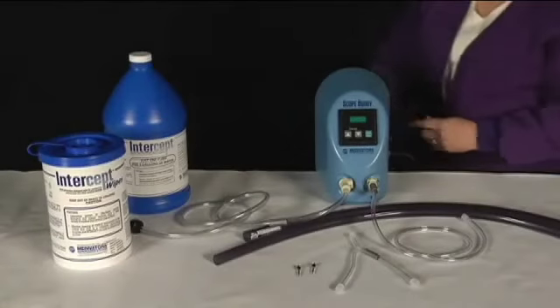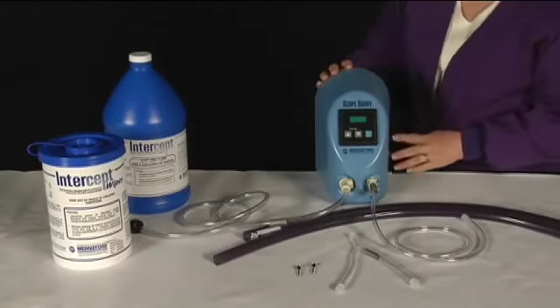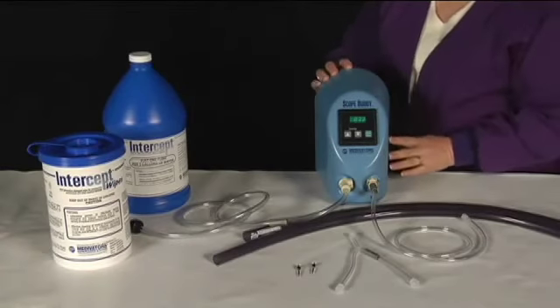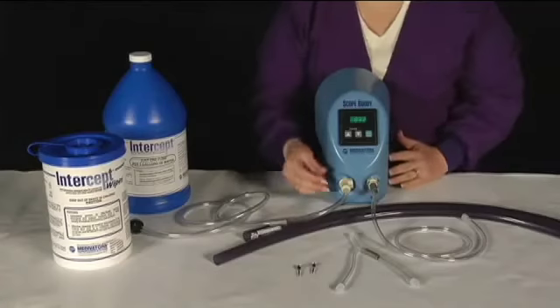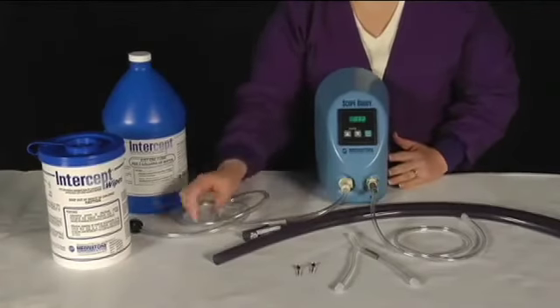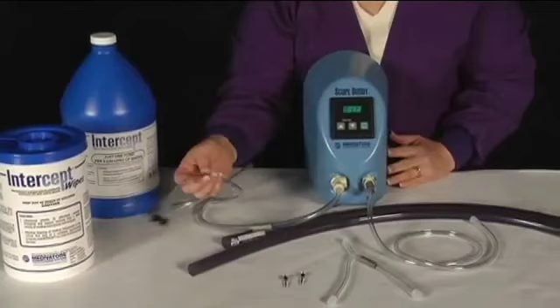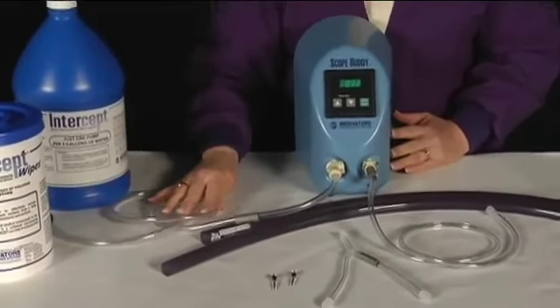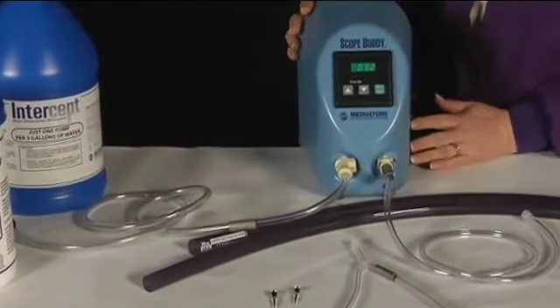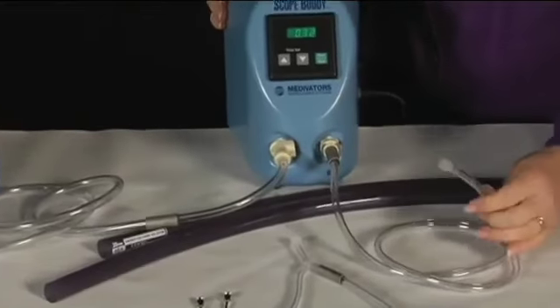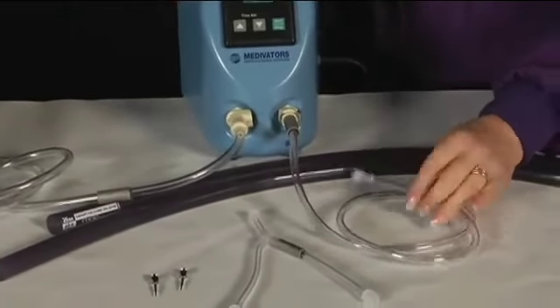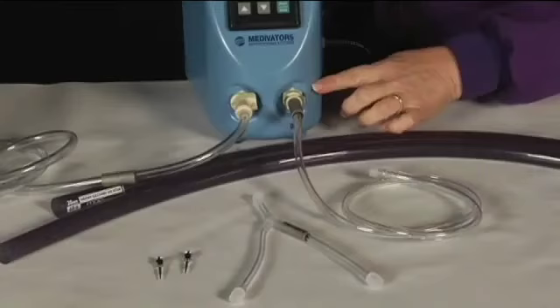Scope Buddy can also be used to flush Savary dilators. Plug the unit in and turn the device on by pressing the power switch. Snap the connector of the fluid intake line to the connection port labeled in and fully submerge the screened end in a sink or basin of detergent solution. Snap the connector of the universal cleaning adapter extension line to the connection port labeled out.